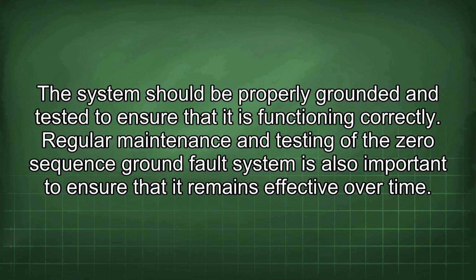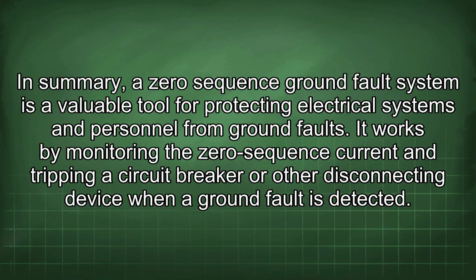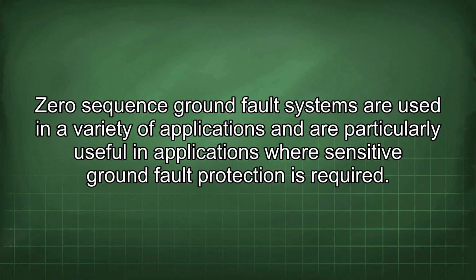Regular maintenance and testing of a zero-sequence ground fault system is also important to ensure that it remains effective over time. In summary, a zero-sequence ground fault system is a valuable tool for protecting electrical systems and personnel from ground faults. It works by monitoring the zero-sequence current and tripping a circuit breaker or other disconnecting device when a ground fault is detected. Zero-sequence ground fault systems are used in a variety of applications and are particularly useful in applications where sensitive ground fault protection is required.